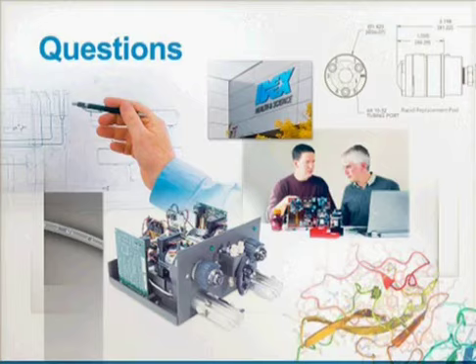And I would just add also that our experience has taught us that when you get down to the lowest flow rates, we can typically really monitor microliter and below. Really, we're talking about precision, and you talked about it earlier in the program today. You can't talk about accuracy at that kind of flow rate because you're talking about the limits of the measurement devices and a number of other things, even in terms of your measurement precision. So I think what we're saying is that at this flow rate, the flow sensing devices that we couple to our pumps do really well at doing that kind of precision and stability that Dave talked about in the online digestion work. Yeah, absolutely.